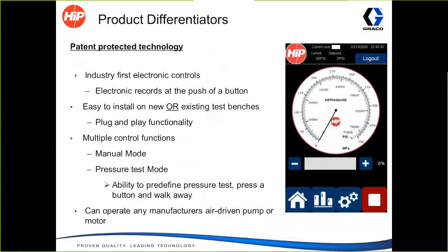The box is going to allow you to record your pressure test, so it takes all the manual work out of it. It's easy to install, whether it's new or on an existing test bench, and it's plug and play, so it's a really easy interface. It's a touchscreen interface that allows you to enter in your parameters, start your test, and walk away and let the control box do its thing. There's a manual mode and a pressure test mode, so you can run the box in those 2 modes. And the control box can be utilized with any high pressure intensifier pump in the market.